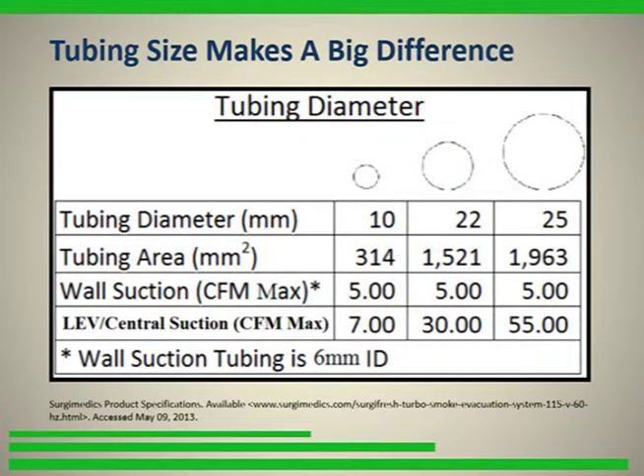The other issue is the physical principle, and that is how much airflow can you get through a certain size tubing. So this table shows the 3/8 inch tubing, which is about 6 millimeters in internal diameter. This is what's attached to the ESU pencil. It shows the 22 millimeter diameter tubing, which is what we commonly call the wand, and you can certainly follow the plume of smoke as it's being produced, but it takes somebody to do that. Or the 25 millimeter tubing, which is 1¼ inch tubing. And you can see as you follow along that the tubing area rapidly increases with size.